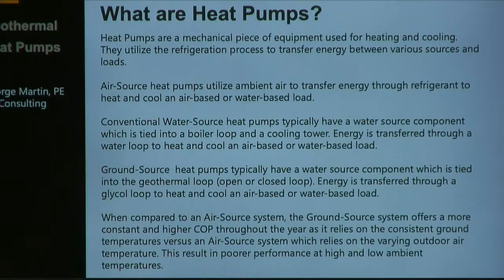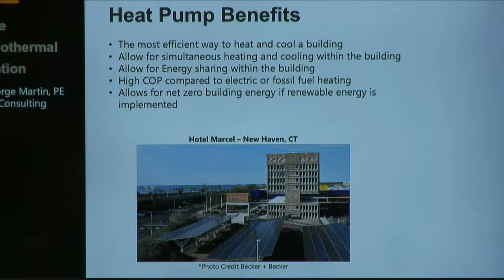So we can move on to the next slide here. Heat pump benefits — this is air source as well. They are the most efficient way to heat and cool a building. They allow for simultaneous heating and cooling, and they allow for energy sharing, which is pretty important for a building like this. There's a lot of internal gains, but you can use some of the heat rejected from cooling to heat domestic hot water for kitchens, etc. So there's a lot of opportunities to share that energy, which only helps from an efficiency standpoint — a great way to use this technology for this building.